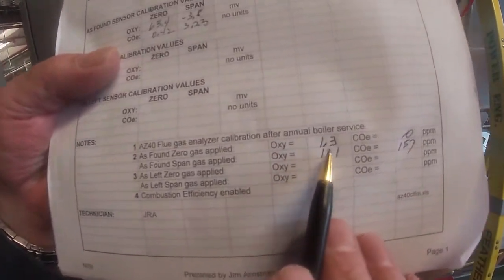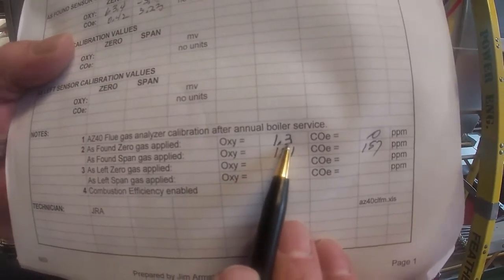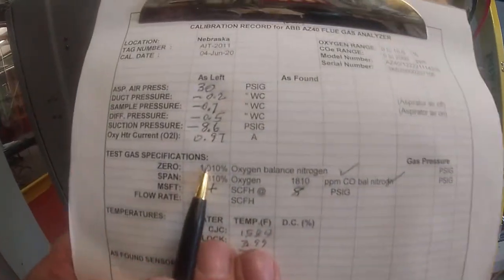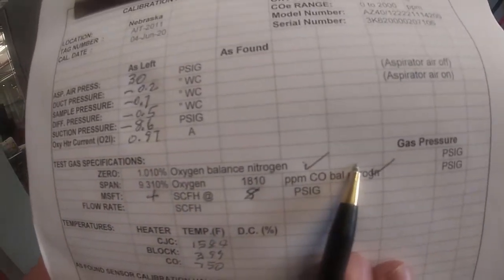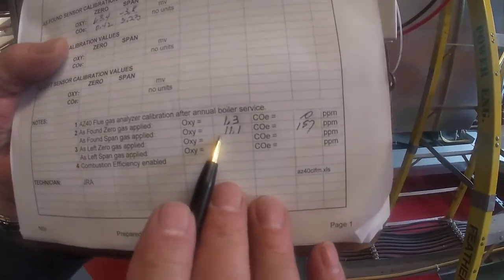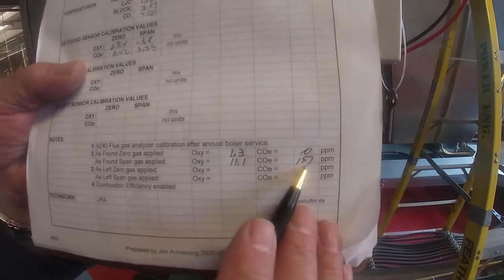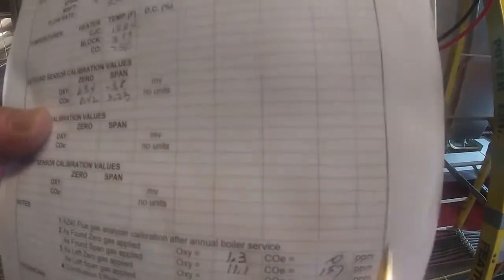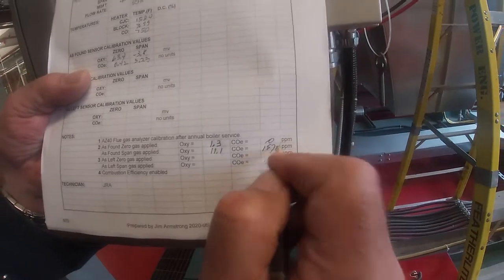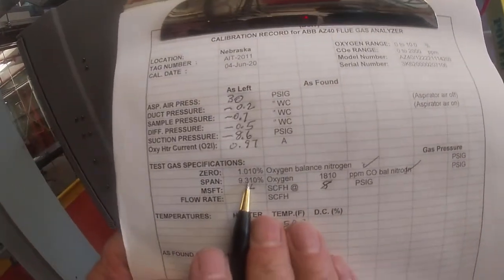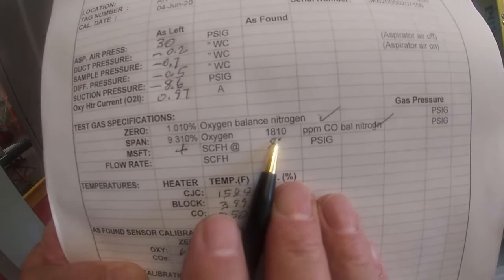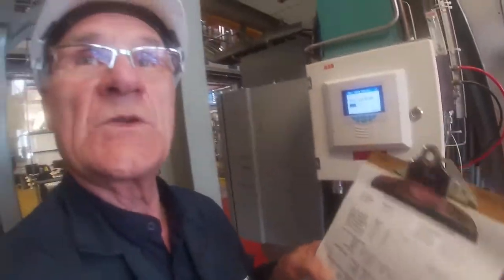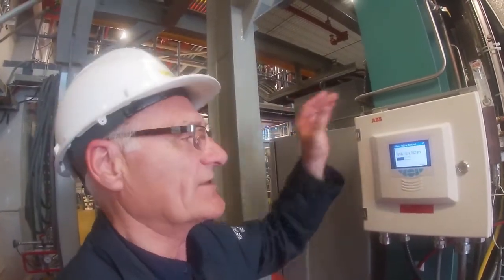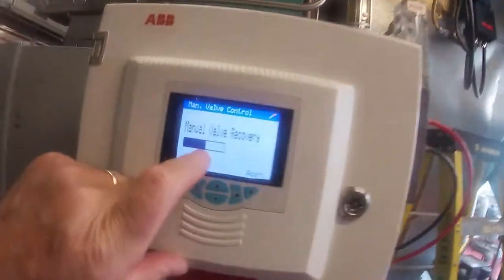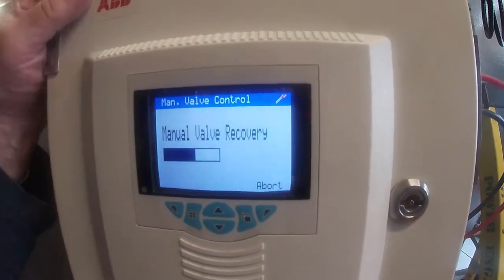On my sheet, it's telling me that my zero gas, we got 1.3 and 0, and we should have, according to the bottle, been a 1.01 and no CO. And down on this one, the span gas was 11.1 with 157 ppm CO, 1570, I forgot to put the 0 in there, and we should have been at 9.3 and 1810. So they're a little bit out of calibration, which gives us a reason to actually do this calibration. Right now, my manual recovery is only halfway through, so we can shut this off.